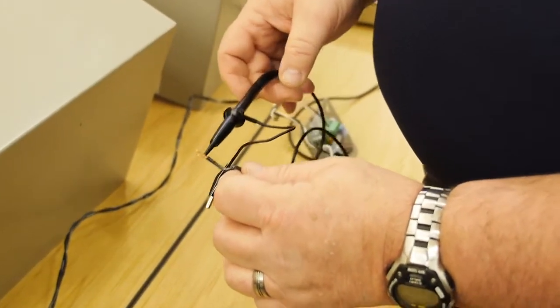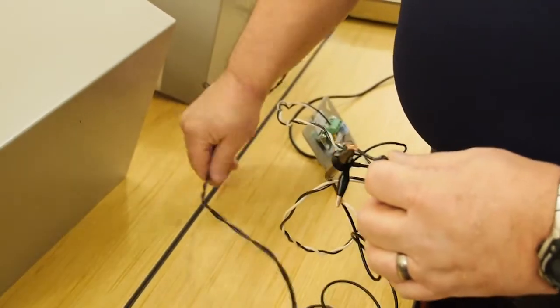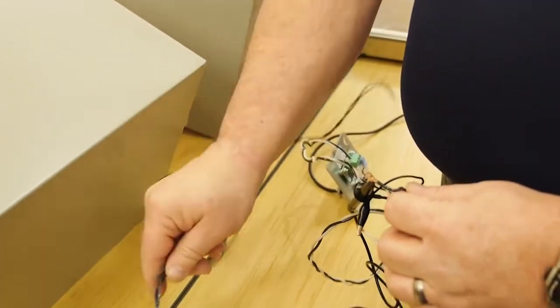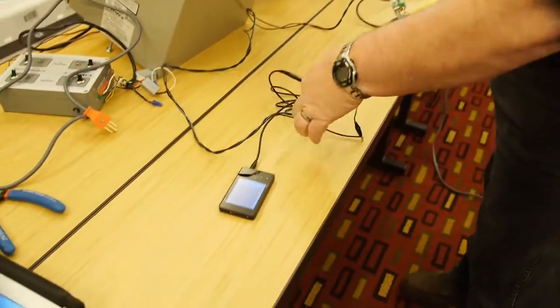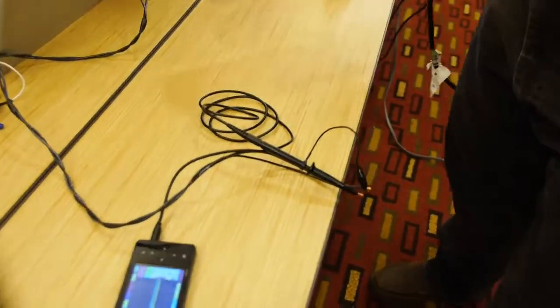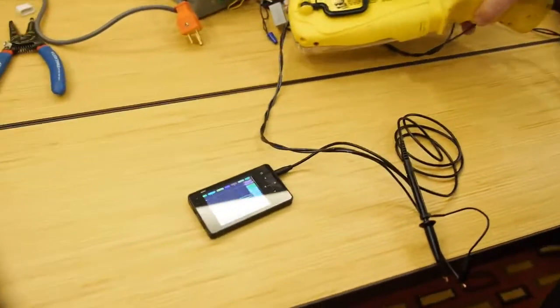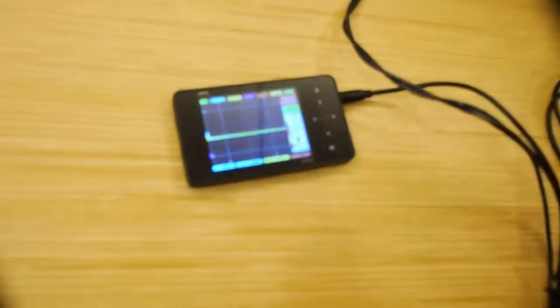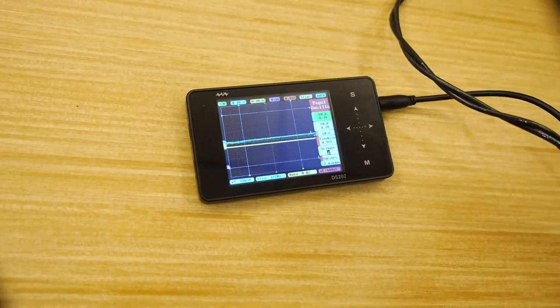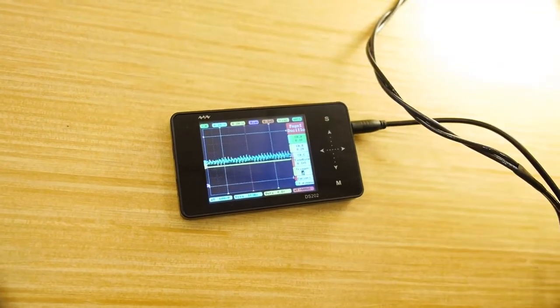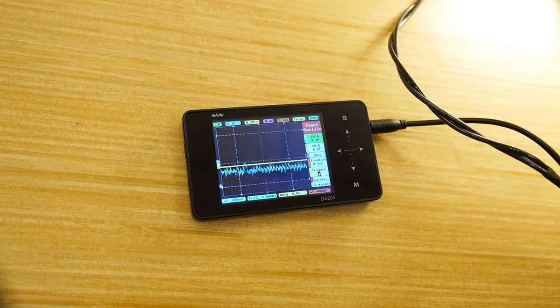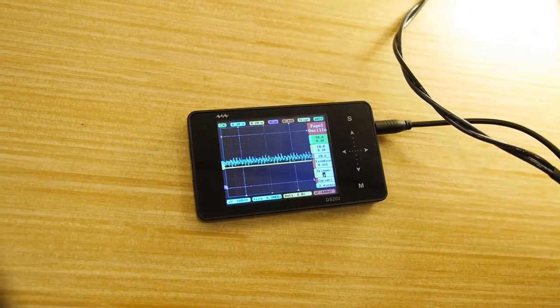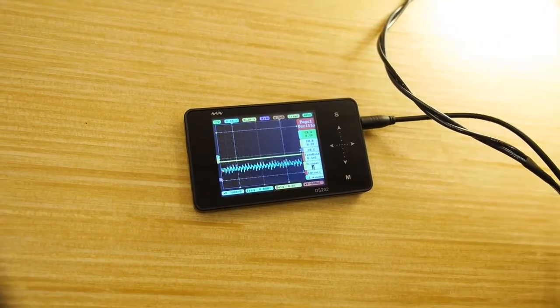So what we're going to do next is hook up some unshielded wire and show you the difference between noise on unshielded wire and noise on PROFINET wire. Now we've hooked up some unshielded wire the same way. Now we're putting a light next to the wire unshielded. You can see we're already seeing noise even without the light being turned on. So now I turn the light on and look at how much noise we're seeing. This is unshielded wire. So if you're using unshielded wire for PROFINET, you're already introducing noise into the system.